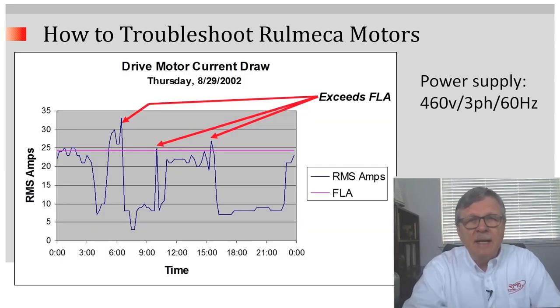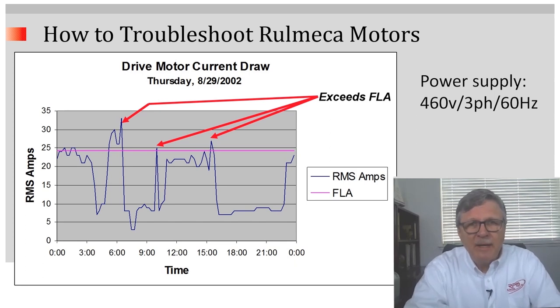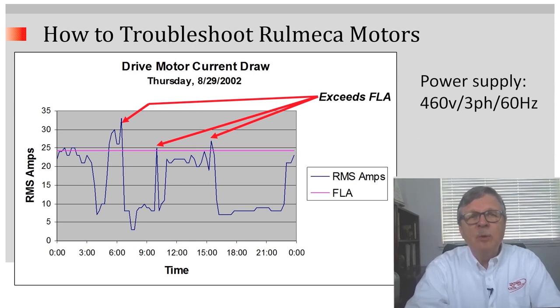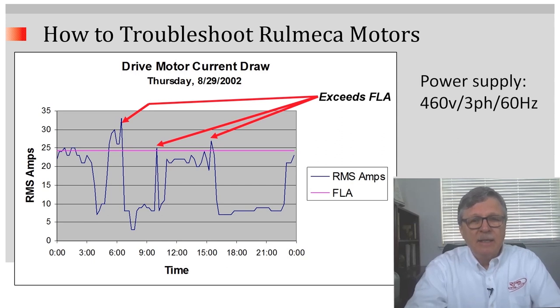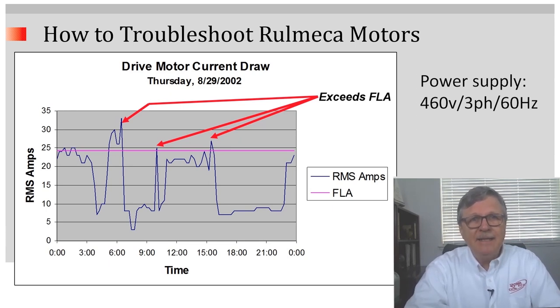Remember the example presented previously — a 20 horsepower motorized pulley driving a conveyor with a full load amp rating of 23.6 amps. This is an actual example of a conveyor being driven by a 20 horsepower motorized pulley over a 24-hour period a few years ago. Notice that it exceeded full load amps several times in that 24-hour period.